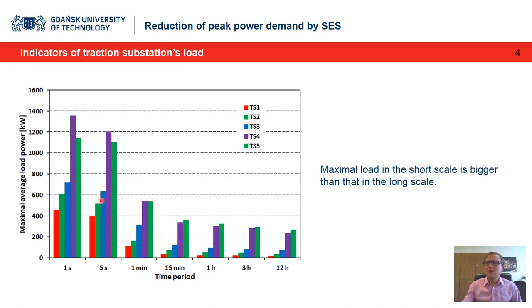I prepared a comparison of some parameters of the maximal load of the traction substation on a long-term scale: the average maximal value of the load in a 1 hour scale and 3 hour period, and on a short time scale: 1 second, 5 second, 1 minute, and 15 minute scales. I made this comparison for 5 traction substations which supply the Gdynia trolleybus supply system.